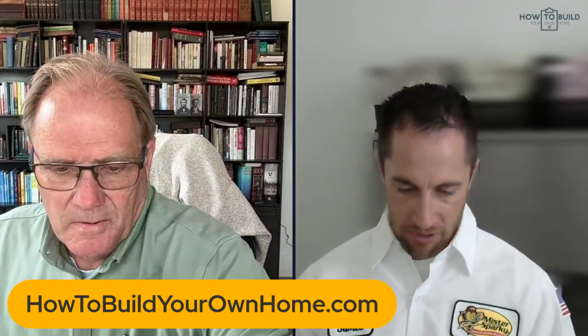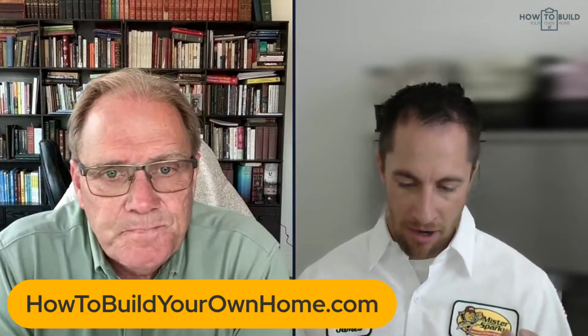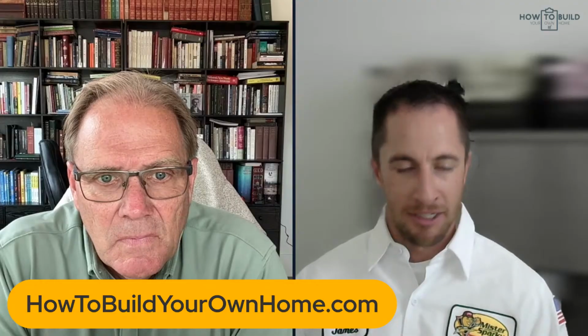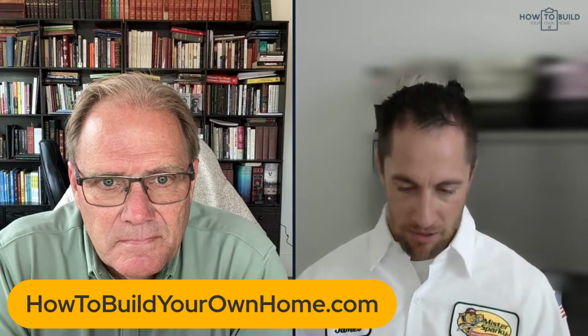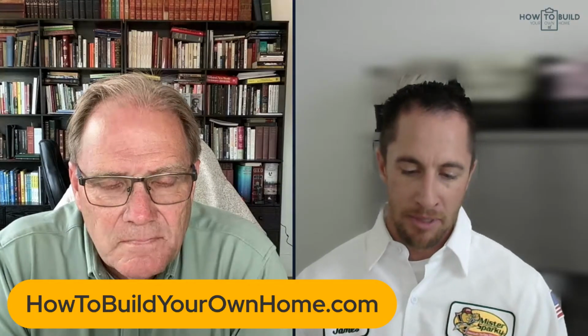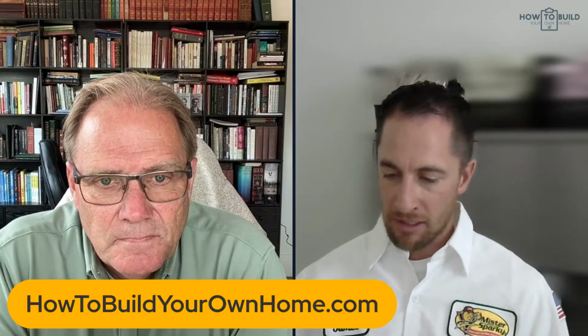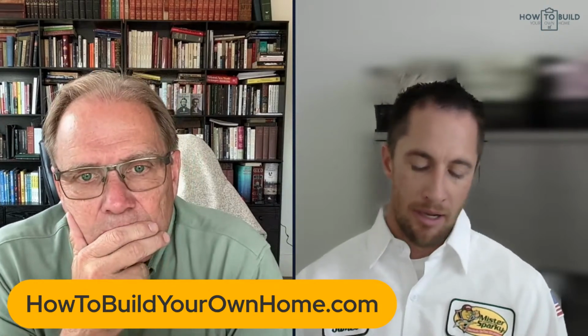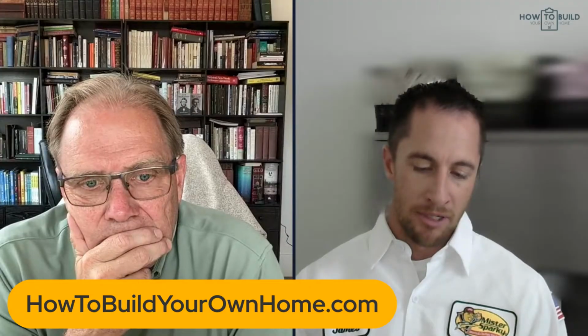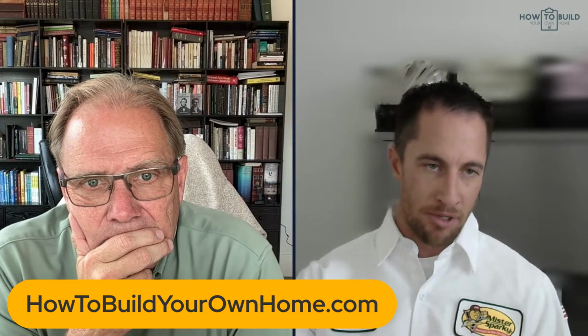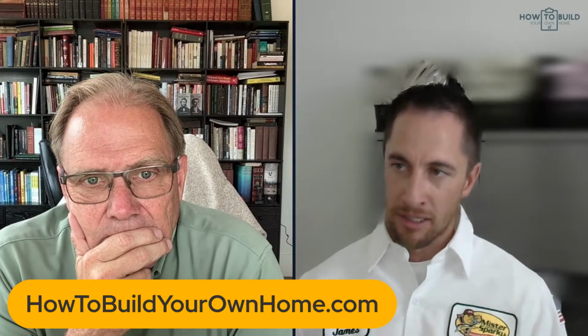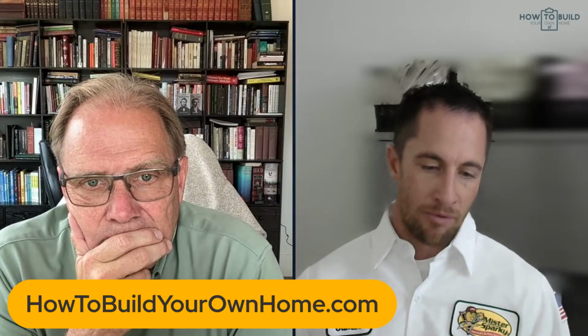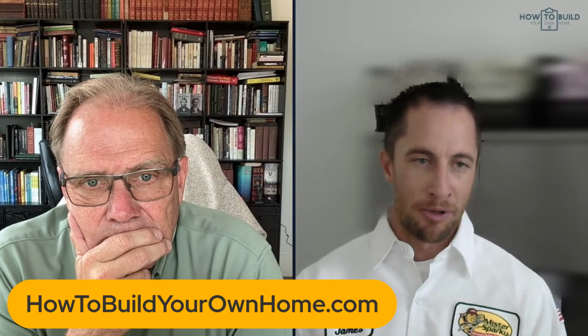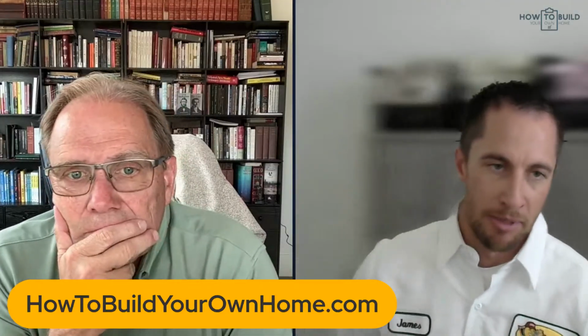You're 100% right. And to add to that, we live in southern Utah where it's a lot hotter, so if you're in a hot climate and your panel sits in the sun a lot, remember that your worst enemy with electrical systems is typically heat. I get lots of service calls for main breaker trips or AC unit trips. The panel is already generating heat, and if the ambient temperature is 110, that breaker might be getting to 150 or 160, degrading the overload and causing more nuisance tripping and more frequent replacement.